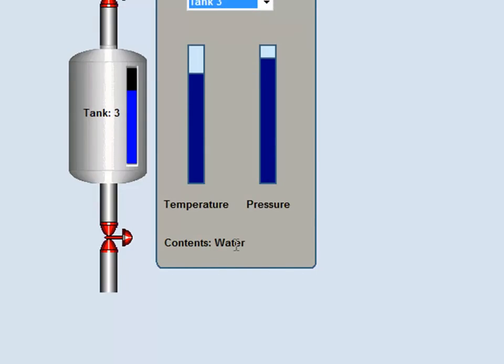Now each one of those could come from a recipe, they could come from a PLC, and we've used a simulation script to simulate this, and that may be controlling these values now. Maybe you don't have the PLC connected. One of the things that you can do, utilizing those same tags, is now disable that script for the simulation. Those tags maybe then could be tied to real-world PLC values, and then you've done some troubleshooting and proven that your tanks work just fine.